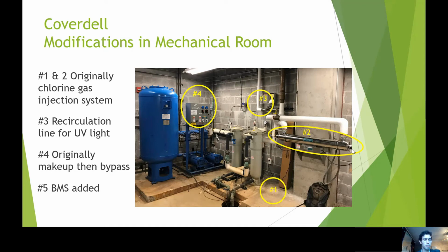And one significant point to take note of is that the system was originally designed to be a makeup system, which means that city water would make up the water inside the tank once it reached a certain low level point. The reason that this system was retrofitted to be a bypass system was in part due to the restrictions a makeup system had on supplying water to the end uses. For example, the system was the sole provider of water to the cooling tower. The cooling tower cannot go without water for more than 2 hours. Otherwise, it will stop functioning as intended for the chilled water system. So it has to always have a constant supply of water.